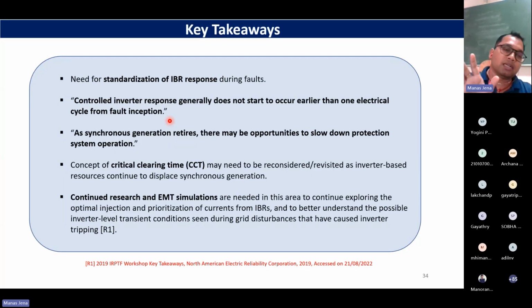Because remember, traditionally the transmission system protections operate the relays within one cycle, they detect within 1 cycle, and the breaker operating time may be 3 to 4 cycles. So within 5 cycles, game over, right? But now, am I going to take a decision within 5 cycles, when my inverter itself is not stable, my inverter itself is trying to track the reference, or the reference itself is trying to change its value based on the POI measurement, right?